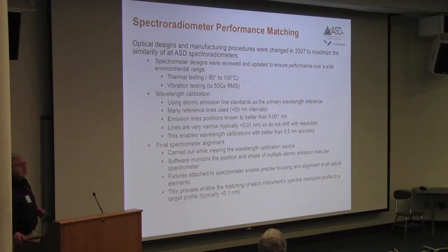Prior to 2007, we used a monochromator that was calibrated to a laser line. But the problem, again, with the monochromator is that in order to get enough light through the monochromator, you have to be allowing a fairly significant peak width through, and there's some uncertainty. There's more uncertainty in the wavelength of your calibration source. So we developed basically a box that had a number of atomic emission line sources in it and we designed our own lamps to get enough intensity, because the standard pen ray lamp that you can get from, say, an optics catalog, particularly at the longer wavelengths, didn't put out enough energy to get a good signal to noise in the lines.